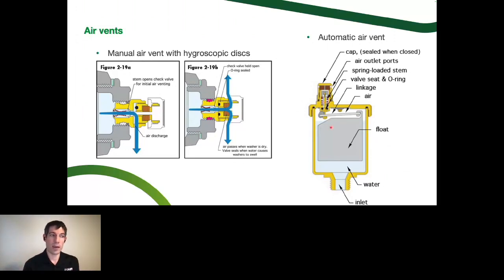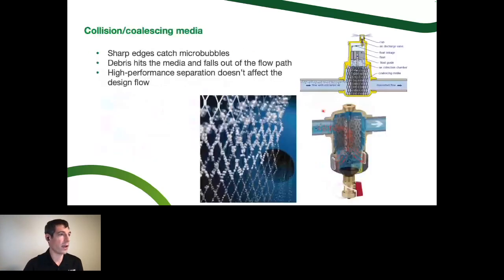The reason that you should not do that, that I know now, is we actually want this little buffer space of air there. So that's how the automatic air vent will work naturally: it's going to leave the water level about an inch, or in a commercial application might be 4 inches, below the needle valve, because we don't want that garbage that's accumulated at the top of the system, like a wood chip or something, that would float to get in contact with the needle valve. So we want that little space in between the needle valve and the line of the water level, so we don't have something get in contact there and get hung up, and that's what would cause an air vent to leak. It can be serviced. You can take that whole cap off, just take some compressed air through that and get the debris out in a lot of cases.